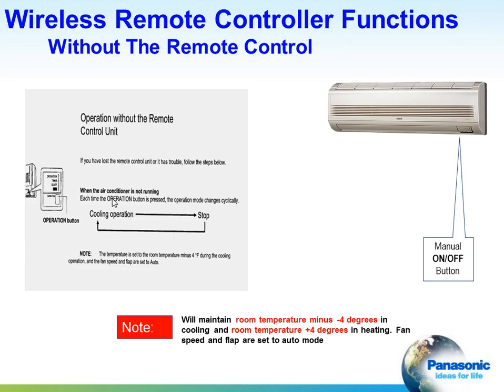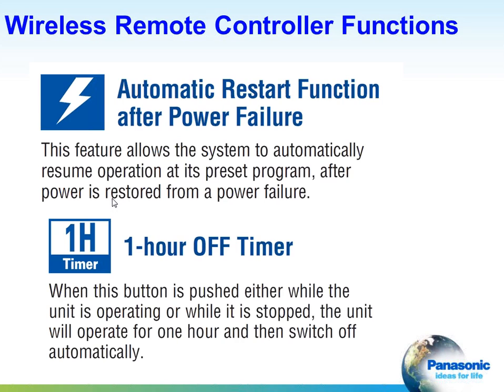You can also control these indoor units by onboard controls on the high wall. Each of these units comes with instructions to accomplish that. There's a number of automatic functions in these controls. The system will restart after a power failure. That's an automatic feature, so you do not have to go out there and reset. You won't get those nuisance calls from the customers. There's also a 1 hour off timer. If you're going to be leaving the space and you want to turn the system off, but you just want to do it before you leave, you can set that to 1 hour, or think of this like an unoccupied hours feature. Punch the button and it will operate for 1 hour.